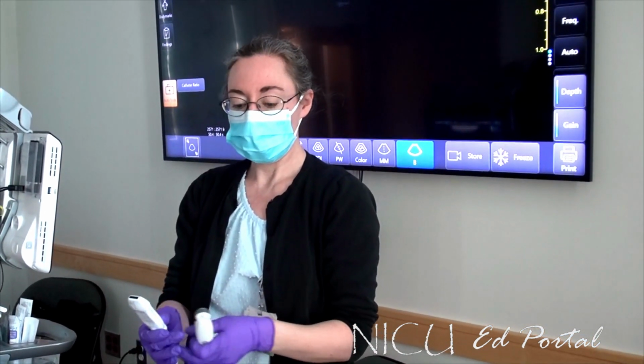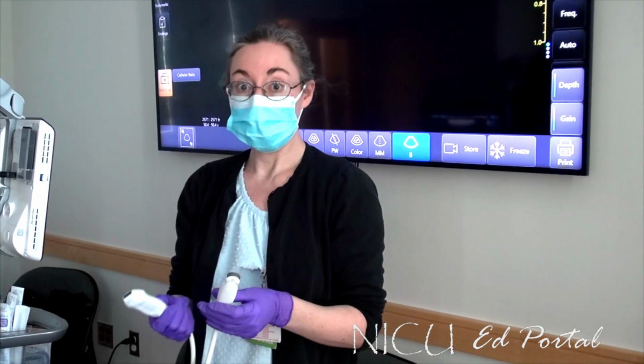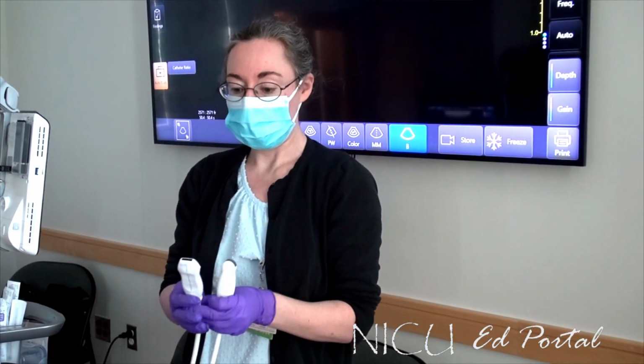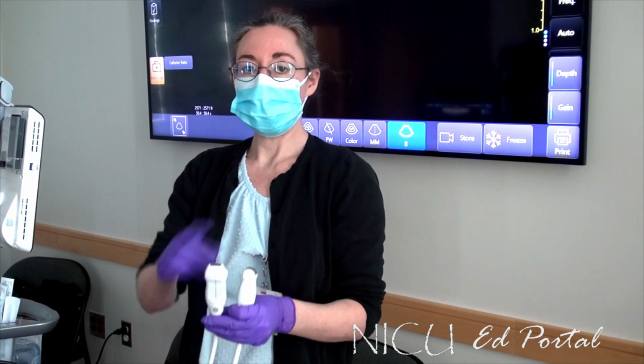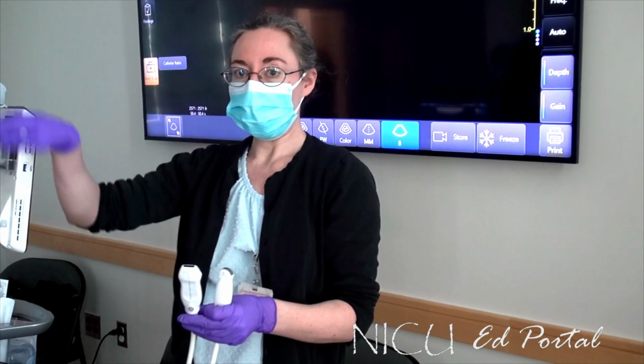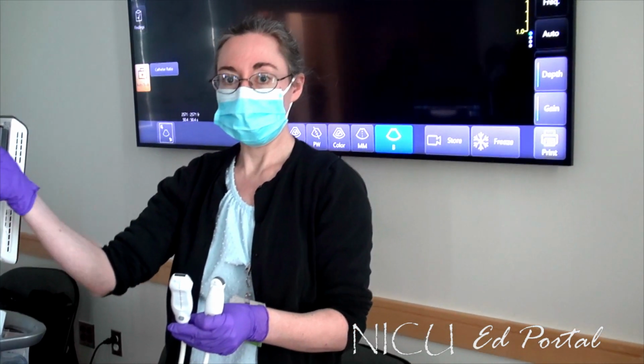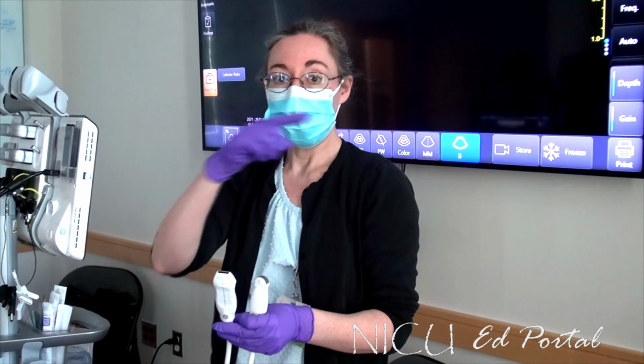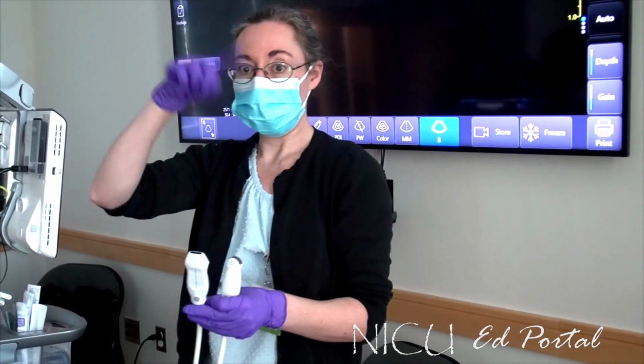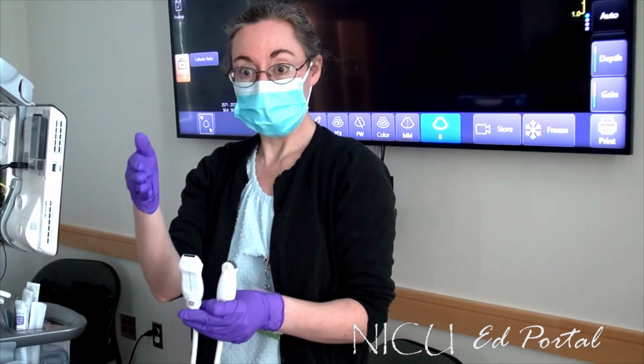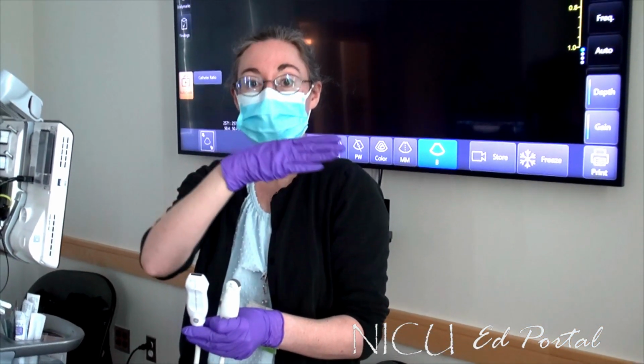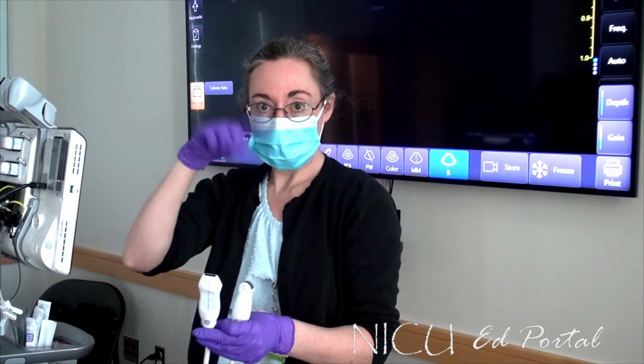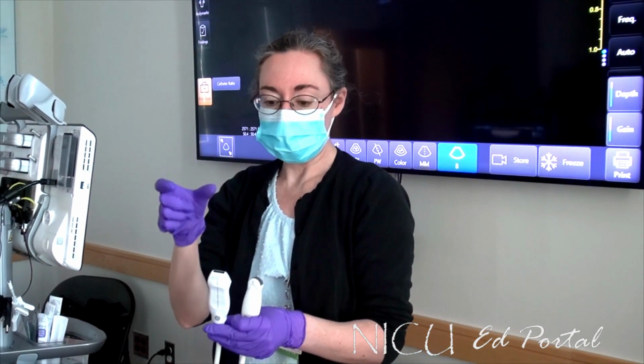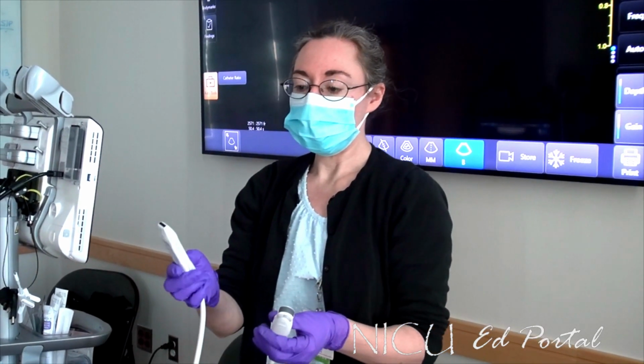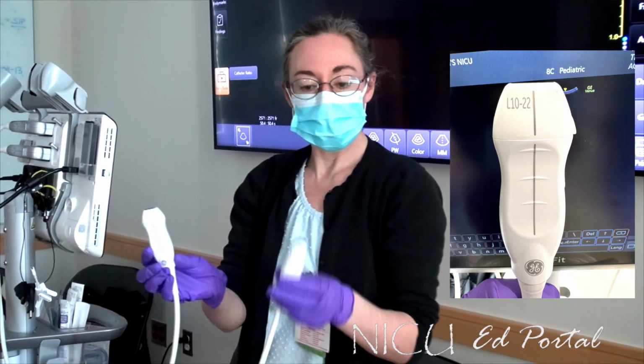In ultrasound, the probes are defined by the frequency of the sound wave that's coming out of the probe. In general, the lower frequency waves tend to penetrate further into the patient before they get attenuated, whereas the higher frequency waves don't penetrate as far, but they hit more structures along the way, so you get more detail.